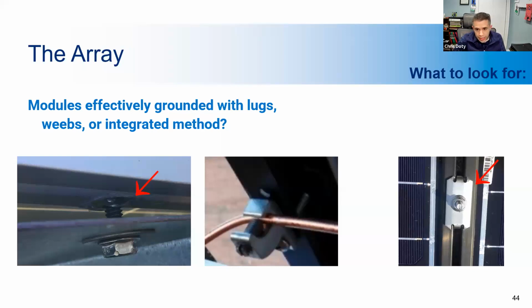So another thing that you want to look at with the array is the grounding of the array. The grounding and bonding of the array is not only a code issue, but a safety issue. The integrity of the grounding system is vital to any electrical installation, not just PV. And the grounding system in a PV system is dependent not only on the conductors, but also on the equipment itself, which is used to carry fault current to an overcurrent protection device or a fault detection system. In the event that there is a breakdown anywhere along the ground fault path, the fault will not be detected, which can leave conductive parts of the system energized and presents a significant shock hazard.